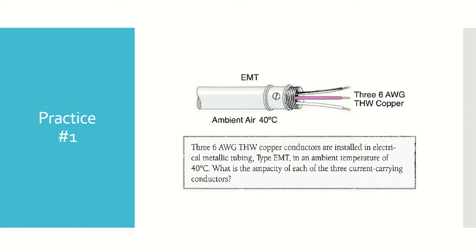ambient temperature of 40 degrees. What is the ampacity of each of the three current carrying conductors? So what are we looking for? First, how many conductors are inside of the pipe? 3. And what's the ambient temperature?